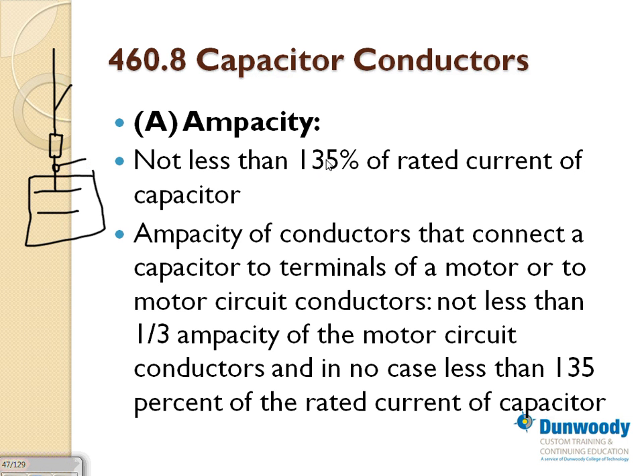If it was a 100 amp capacitor, I like the 100 amp because it's easier. The conductor has to be not less than 135 amp rated. So if it's a 100 amp capacitor, you need a 135 amp conductor. Go to the table that I showed you, use the 75-degree column, size your conductor. Done. How about the fuse?